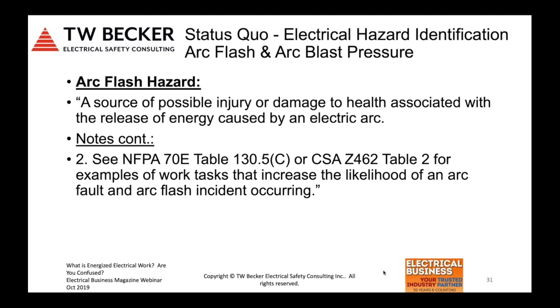And lastly, a table was added in the last two editions of 70E and Z462, Table 130.5(C) in 70E, or Z462 Table 2, that is a work task list that is very helpful for users of the standard when completing an arc flash risk assessment, but it does require assessment of condition of maintenance, and then the table indicates whether the likelihood of occurrence of an arcing fault and an arc flash is yes or no. So again, it is a subjective determination based on risk related condition of maintenance, identifying when an arc flash hazard exists against a defined work task. This is the status quo out there. We've had the latest edition of 70E and Z462 now for almost 2 years, and workers should have been trained on the latest edition, and employers should have adapted this information into their electrical safety programs and into the workflow they apply with their workers, in the context of identifying and then moving through an arc flash and shock risk assessment to determine additional protective measures.